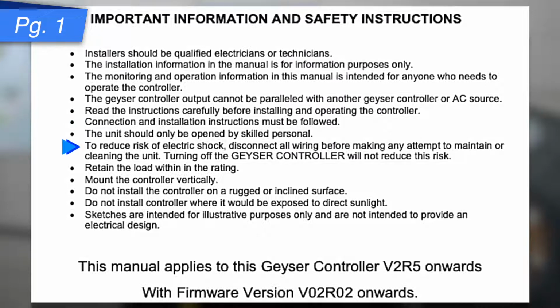Please make sure, to reduce any risk of electrical shock, that you disconnect all wiring before making any attempt to maintain or clean this unit. Turning off the Geyser Controller will not reduce this risk. It's important that you retain the load within the specified ratings that we supply for you in this installation manual. We're going to ask you to mount the controller vertically, preferably at eye sight, so that you can have access to it. Do not install it onto an inclined surface or any rugged surface. It needs to be preferably a nice clean cement wall, where there won't be any sunlight exposed onto the unit. We have given you quite a few instructions and illustrations in this manual to assist you in this regard.